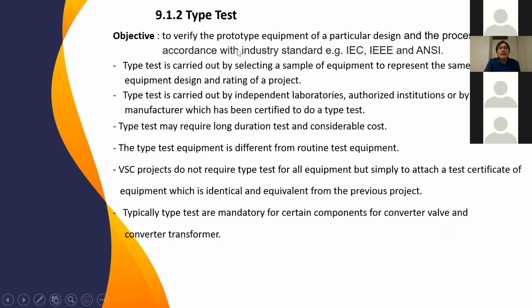Type test is to verify the prototype of equipment. Type test is different from routine test. Type tests are normally carried out by an independent laboratory, and type tests sometimes require long duration and considerable cost. For main equipment, the type test is mandatory during project execution. For instance, for converter valve and converter transformer, there are certain type tests that should be carried out. And then for the rest, we only need to show a type test certificate from a previous project.